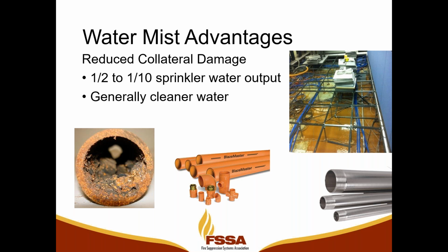My purpose here is to outline some of the primary advantages of water mist. Jonathan alluded to some of them, and then I'll go into a little more depth on the very specific approval protocols that FM has developed for water mist systems. The number one advantage by far of water mist, especially when comparing it to sprinklers, is reduced collateral damage. Both systems obviously have their place and their role. When we want to protect the actual contents of a space, we're going to go with a water mist system because it's going to do a lot less damage to the contents of the space.